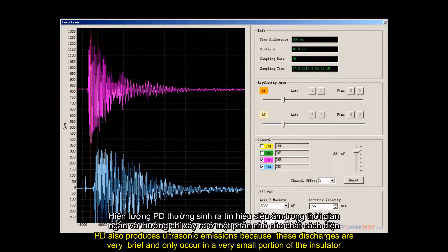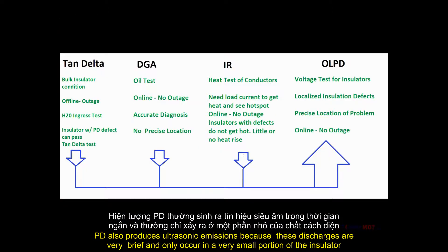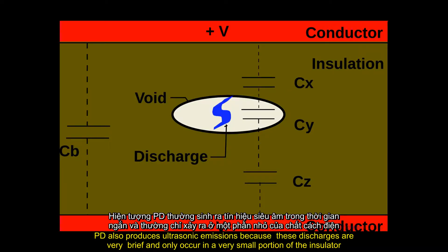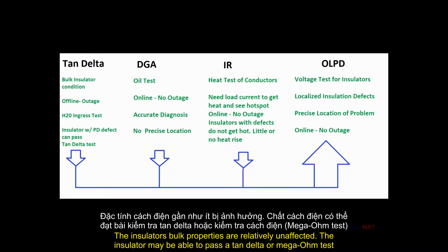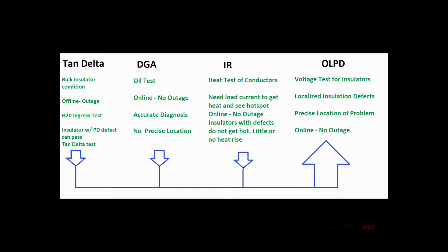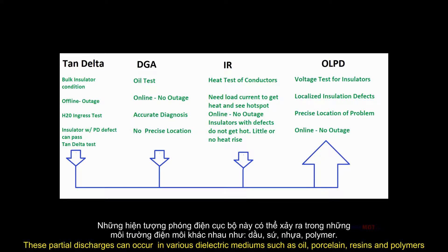PD also produces ultrasonic emissions. Because these discharges are very brief and only occur in a very small portion of the insulator, the insulator's bulk properties are relatively unaffected — the insulator may be able to pass a tan delta or mega-ohm test. These partial discharges can occur in various dielectric mediums such as oil, porcelain, resins, and polymers.